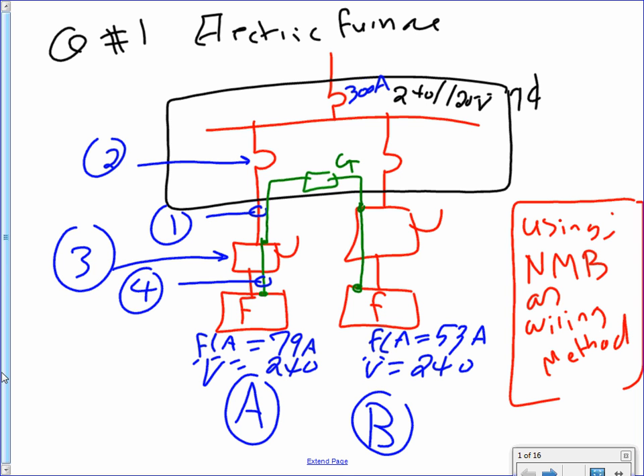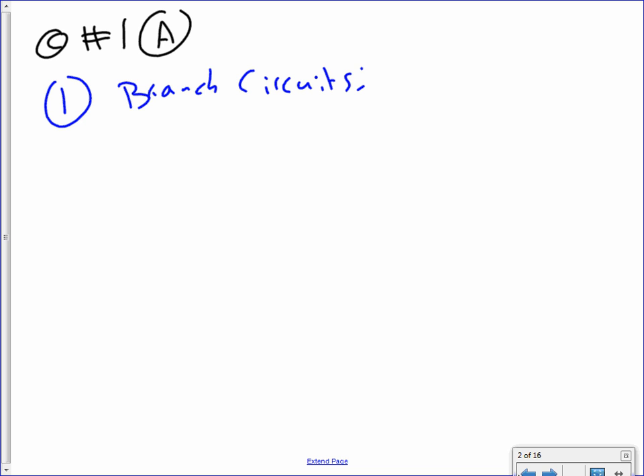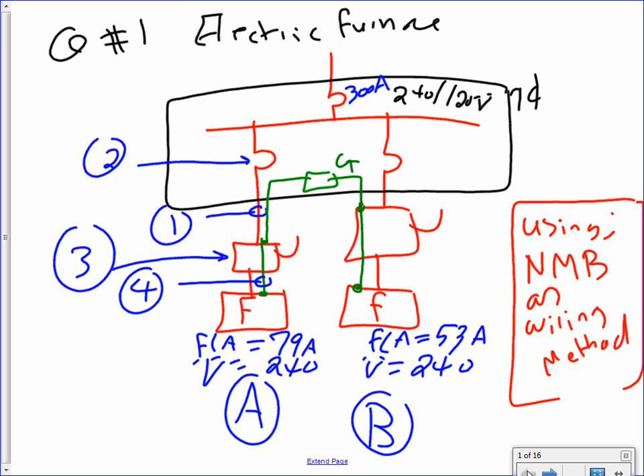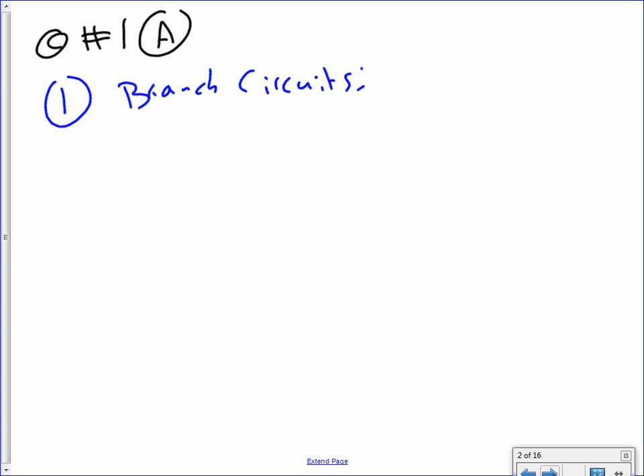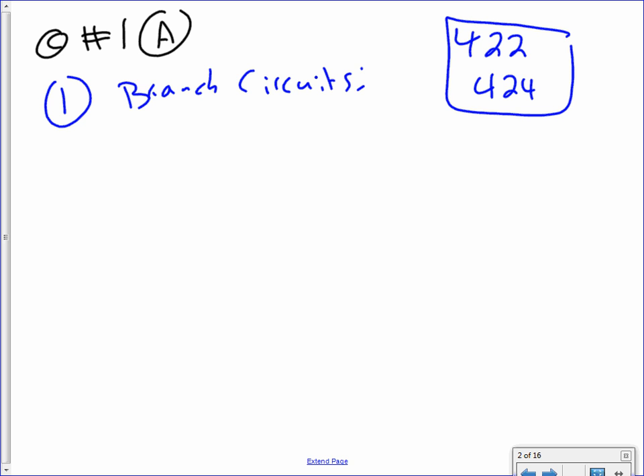These are electric furnaces, and we are to size the disconnect, the overcurrent protection device, the grounding conductor, as well as the ungrounded conductors. Shall we go ahead and start? For both of them, I remind you we're using an NM cable. So the first thing I would like the guys to do is size the branch circuits. Before we go ahead, for electric furnaces, we have appliances. The article that you're going to be dealing with is Article 422. These are appliances, 422 as well as 424. These are the articles that we're going to be pulling information from.